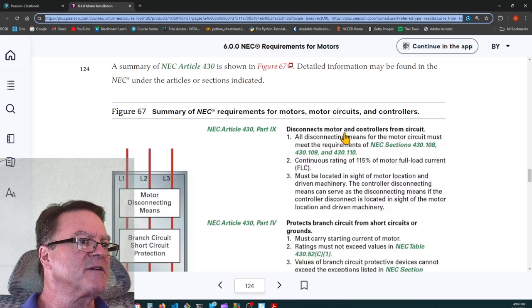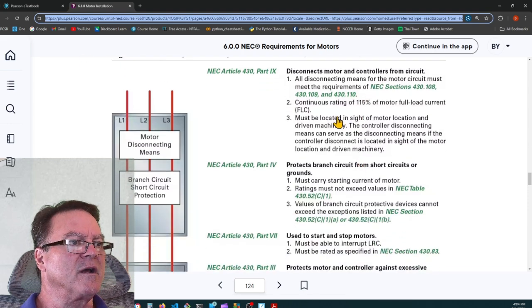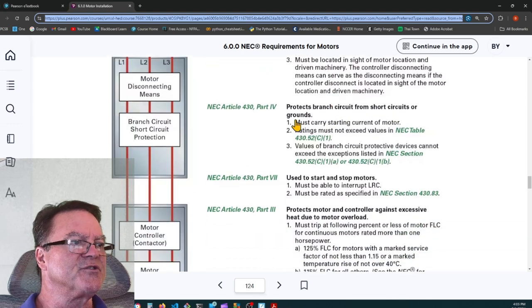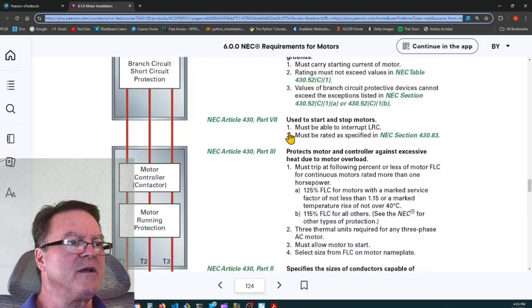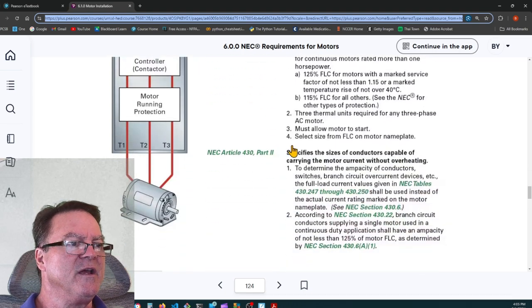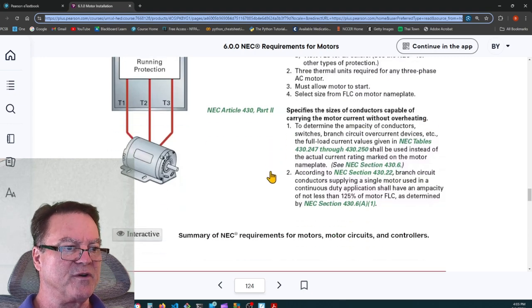So part 9 is disconnect motor controllers from the circuit. All disconnecting means for the motor circuit must meet the requirements of NEC sections 430.108, 109, 110. Continuous rating of 115% of motor full load current and must be located in sight of motor location and driven machinery. Protects branch circuit from short circuits and grounds. That's part 4. Used to start and stop motors. That's part 7. Protects motors and controllers against excessive heat due to motor overload. That's part 3. Specifies the sizes of conductors capable of carrying the motor current without overheating. That's part 2.